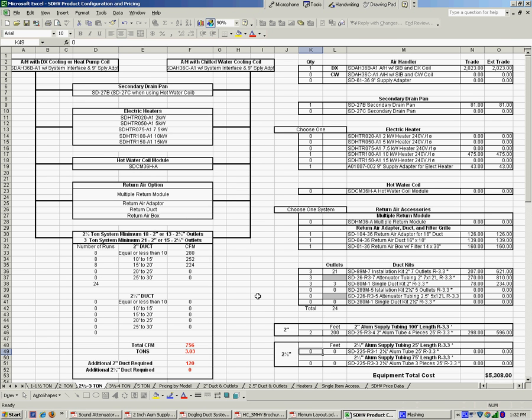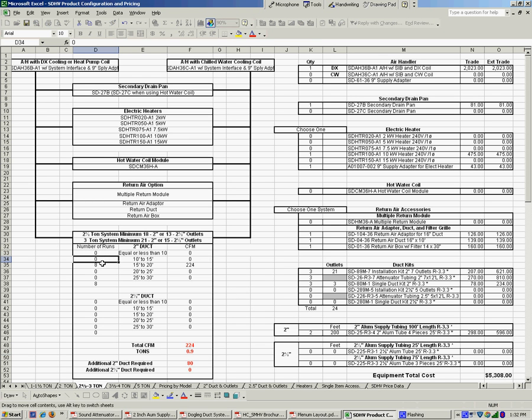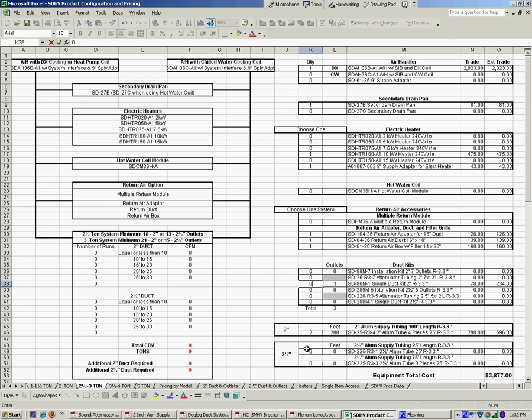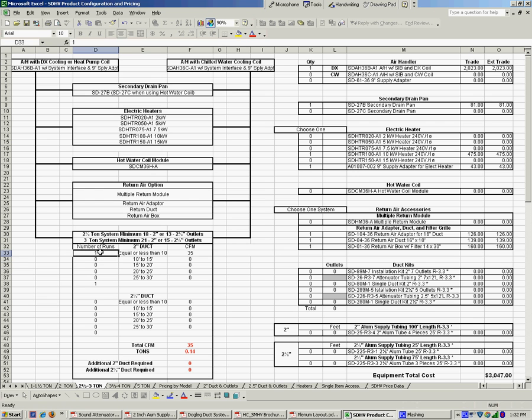Now one of the nice things about the system is we can also have the capabilities on a different size. We can use a 2.5 inch. The benefit here is that we can do a little more air out of the 2.5 than we can out of the 2. So let's reset this. And we'll get rid of all of the 2 inch duct. And just to give you an example, a single run of 2 inch is going to give me 35 CFM, whereas a 2.5 inch is going to give me 45.